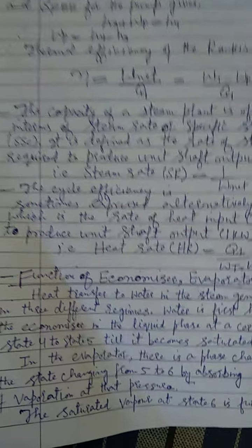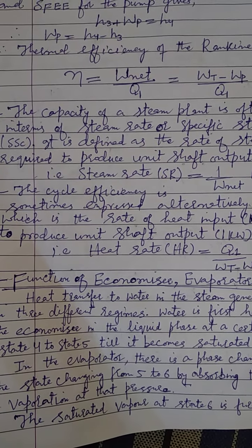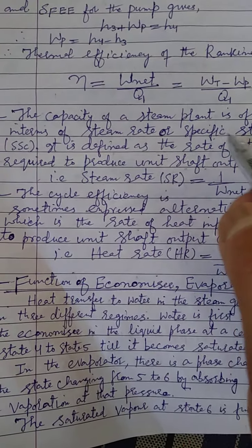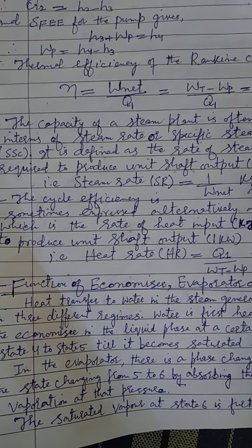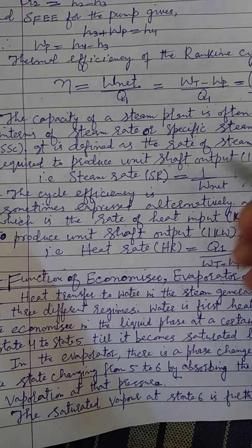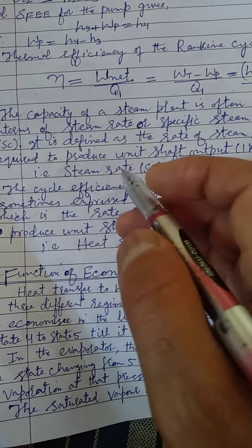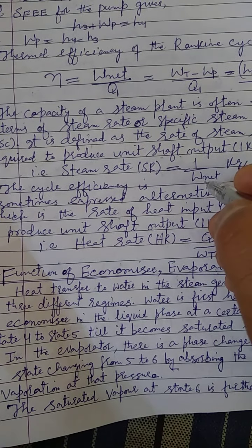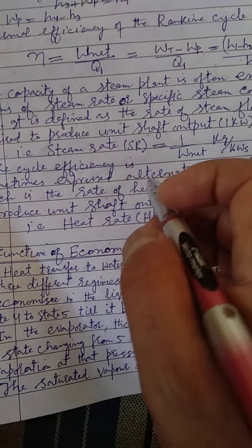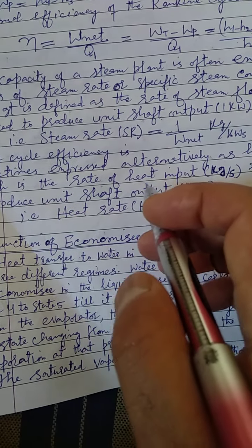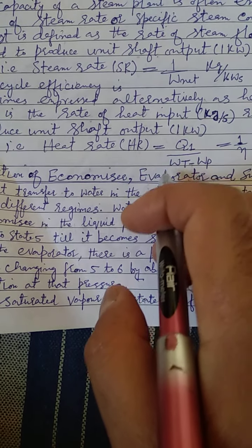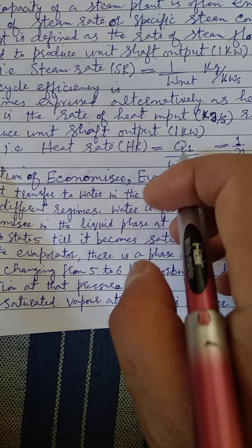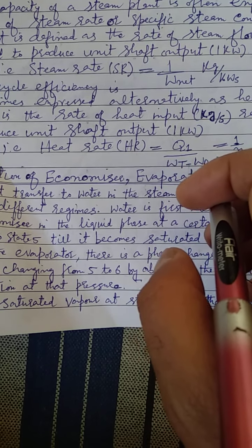Sometimes we need to express the capacity of a steam power plant. The capacity is often expressed in terms of steam rate or specific steam consumption (SSC), defined as the rate of steam flow in kg per second required to produce unit shaft work of one kilowatt. Steam rate SR equals 1 divided by net work done in kg per kilowatt-second. Cycle efficiency is also expressed as heat rate, which is the heat input required to produce one kilowatt of shaft output, equal to heat input divided by net work done. Heat rate is the reciprocal of thermal efficiency.